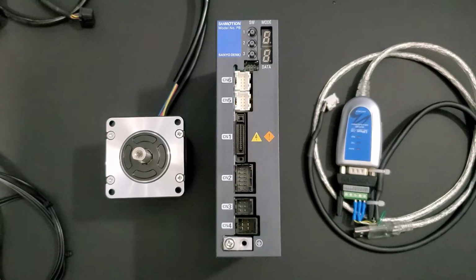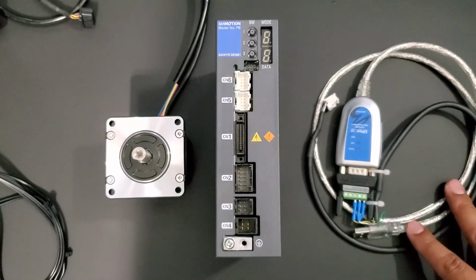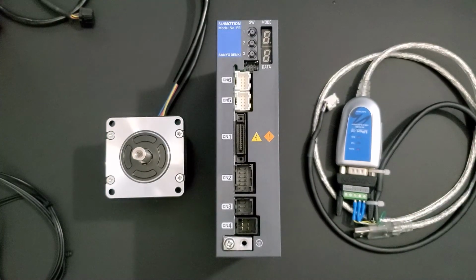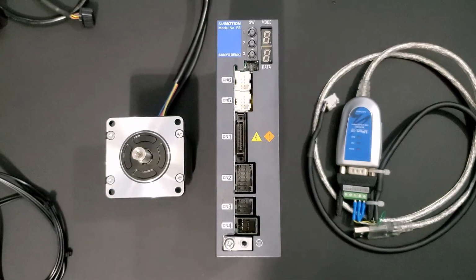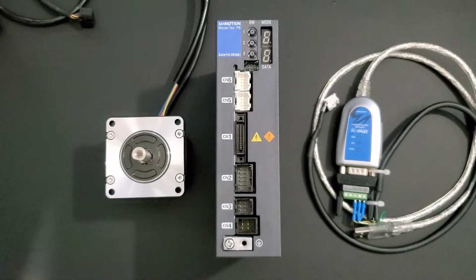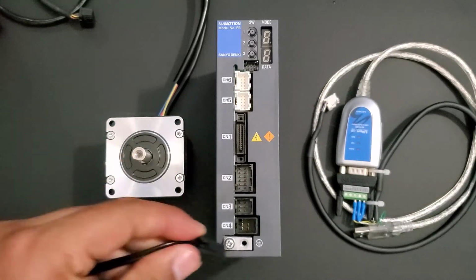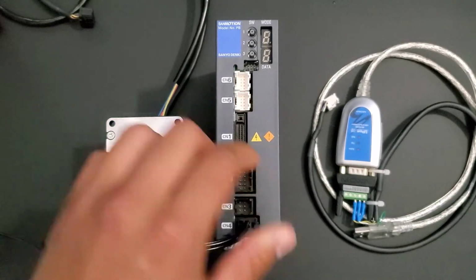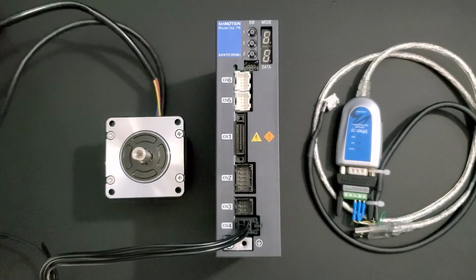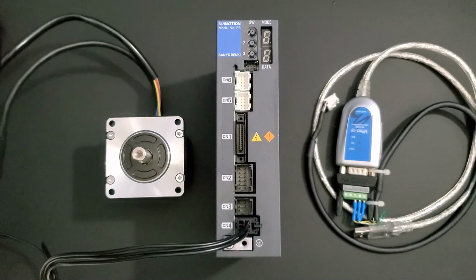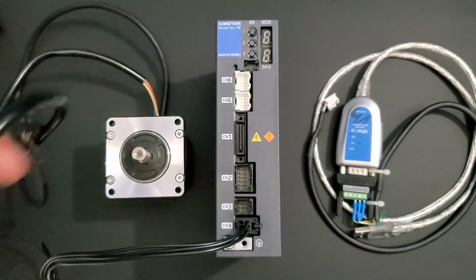If you need any help with the wiring diagrams of main input power or input and output or the communication cable, please click the link in the description, which will show you all the wire diagrams you need to use this drive properly. Once you are done with the wiring, you could connect your main input power, your motor power connector, and your motor encoder connector.